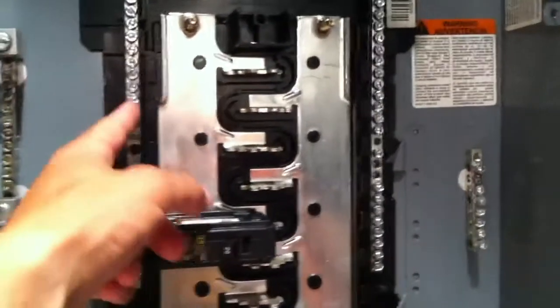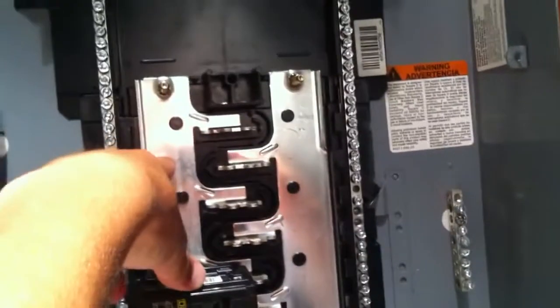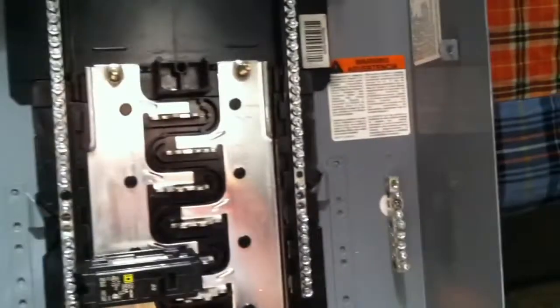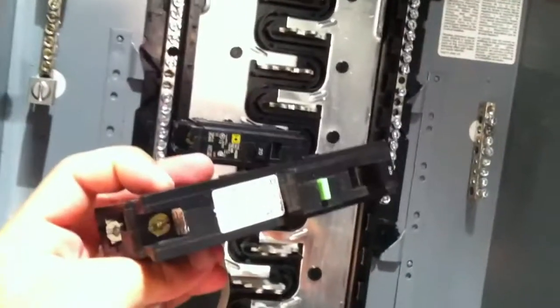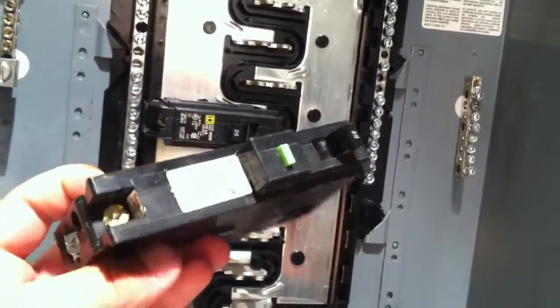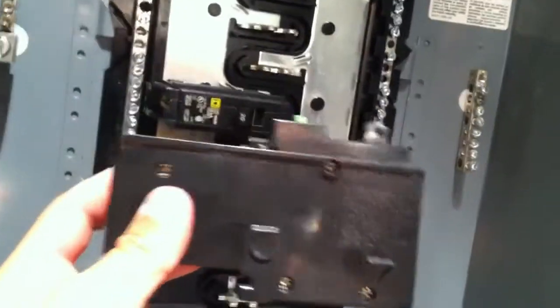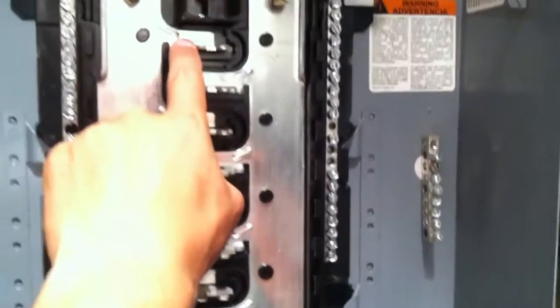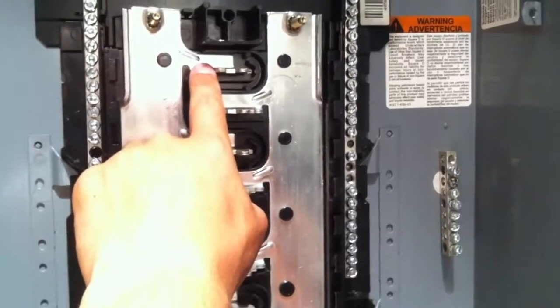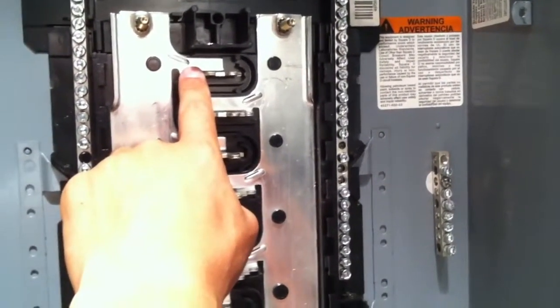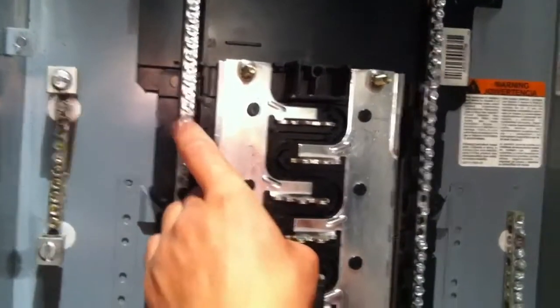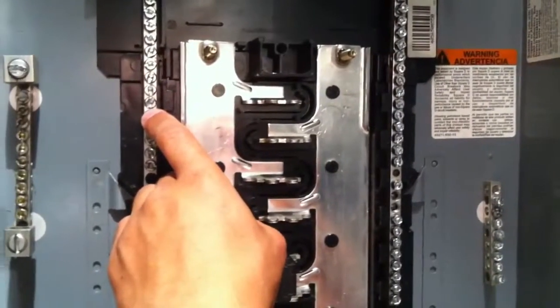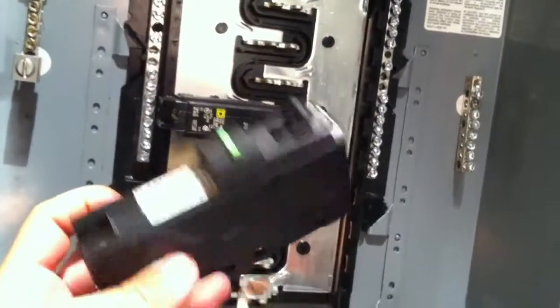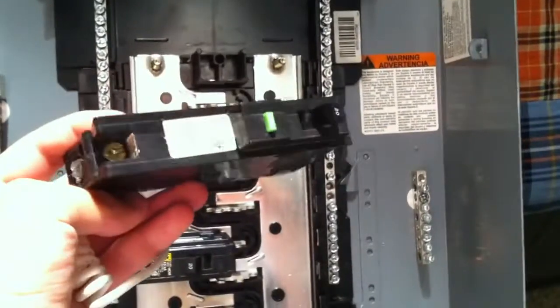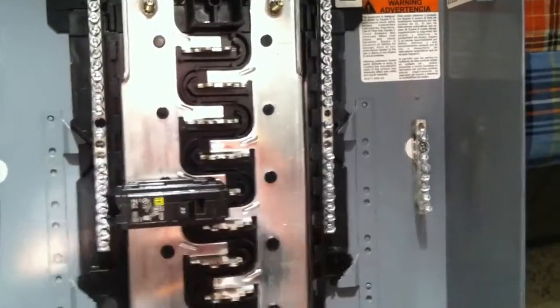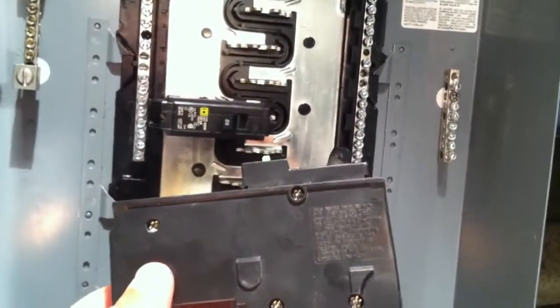So you have 14 amps coming back through your neutral from that circuit, but you're putting out 15 amps. That's not good. That means an amp of current is being lost somewhere. This breaker will immediately trip. Now, that's a lot of current. An amp is a lot. These breakers typically trip if they detect 30 or 40 milliamps of difference. So let's just say 13.2 amps are coming in here, and only 13.1 are coming back to this neutral. This breaker would immediately detect that 0.1 amp and shut off immediately. That's a safety measure, since 100 milliamps of current is being lost somewhere. That could be an arc, it could be a ground fault, it could be whatever.